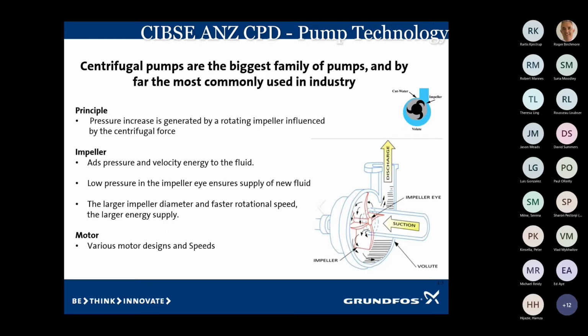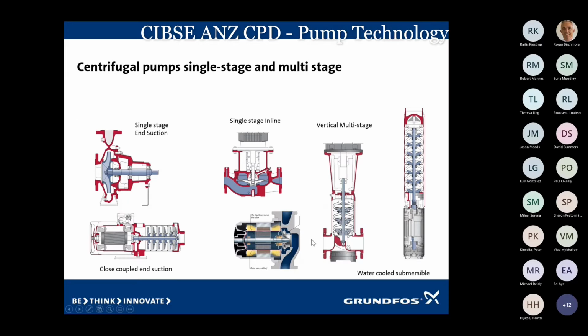If we look at centrifugal pumps, we also have displacement pumps. For us, most of our pumps really are centrifugal type pumps, single stage and multi-stage. The principle behind the pump is to take the water into the suction port and deliver it out through the discharge. And the motor driving on the other end, depending whether it's a 2-pole or a 4-pole, will depend on the head that the pump can actually produce. So the 1450 or 4-pole motor will produce a lower head than the 2-pole.